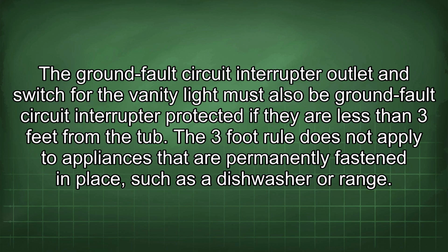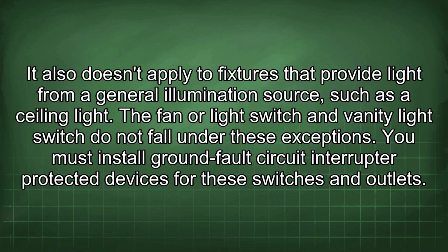The 3-foot rule does not apply to appliances that are permanently fastened in place, such as a dishwasher or range. It also doesn't apply to fixtures that provide light from a general illumination source, such as a ceiling light. The fan or light switch and vanity light switch do not fall under these exceptions. You must install ground fault circuit interrupter protected devices for these switches and outlets.